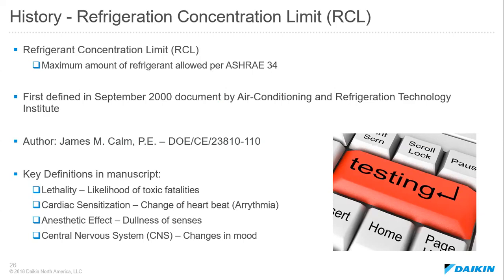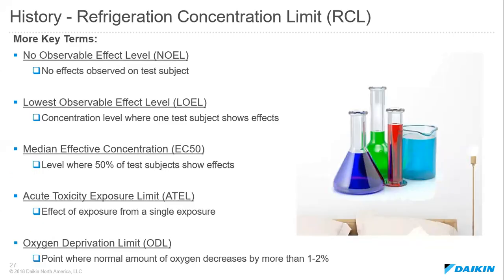And the goal of this document was to define for refrigerants things such as lethality, which is the likelihood of toxic fatalities; cardiac sensitization, change of heartbeat or arrhythmia; anesthetic effect, which is the dullness of the senses; and it also defines the central nervous system effect, or how the refrigerant might change mood. And as I show my icon here, they actually did testing. This testing was actually done on mice, and this testing then was compared back to humans, and how it might affect occupants in the space. Some more key terms related to the history of the refrigerant concentration limits include a term called no observable effect level, or the NOEL, which basically says there were no effects observed.